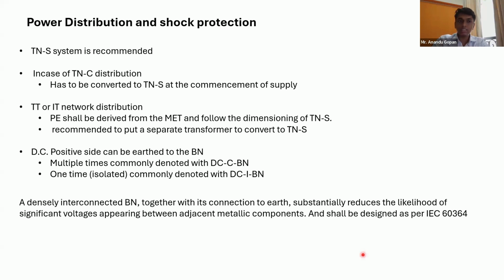But using TNC inside your building is strictly prohibited. You are not supposed to use it. And then you have your TT and IT. If you are going to use TT or IT, the PE conductor, you can derive it from the MET obviously. And this PE conductor sizing must be as per TNS system. And then it's recommended to have your own transformer and convert it again into a TNS, because in TNS you have a separate fault return path.